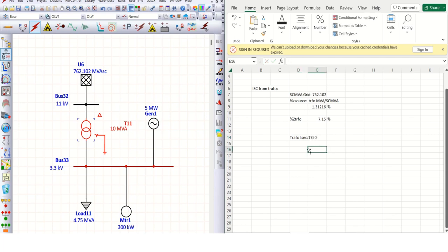So your ISC from trafo, that is contribution from transformer, is going to be 1750 divided by the sum of these two values, this one plus this one. These two values are in terms of percentage, so I want to multiply by 100 in the numerator. So this is the contribution from trafo.